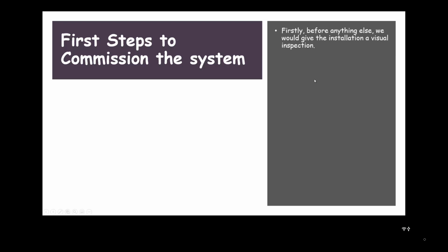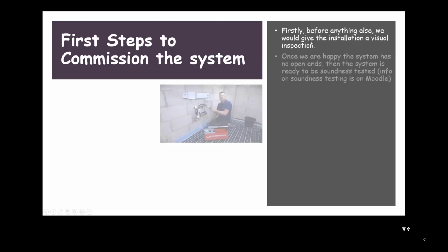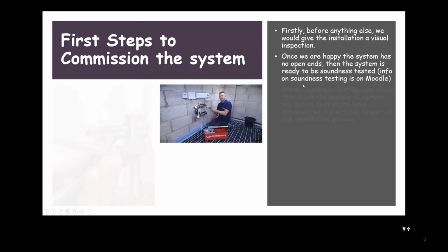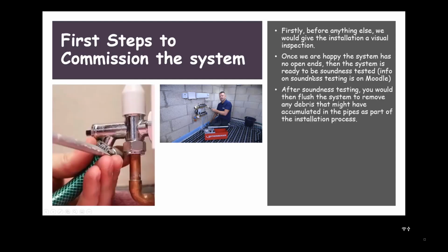So our first step, as we've discussed, is a visual inspection. Once we're happy the system's got no open ends and no obvious issues with it, then we know that it's ready for soundness testing. The information on soundness testing for a rigid pipe and plastic pipe is found on our Moodle. After the soundness test, you then flush the system, and that would remove any debris that might have built up in the pipes as part of the installation process.